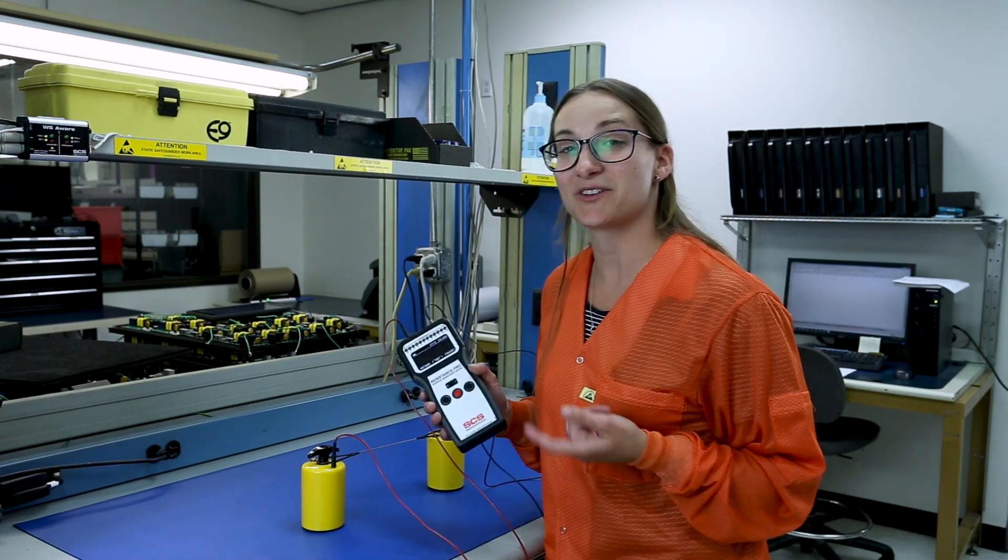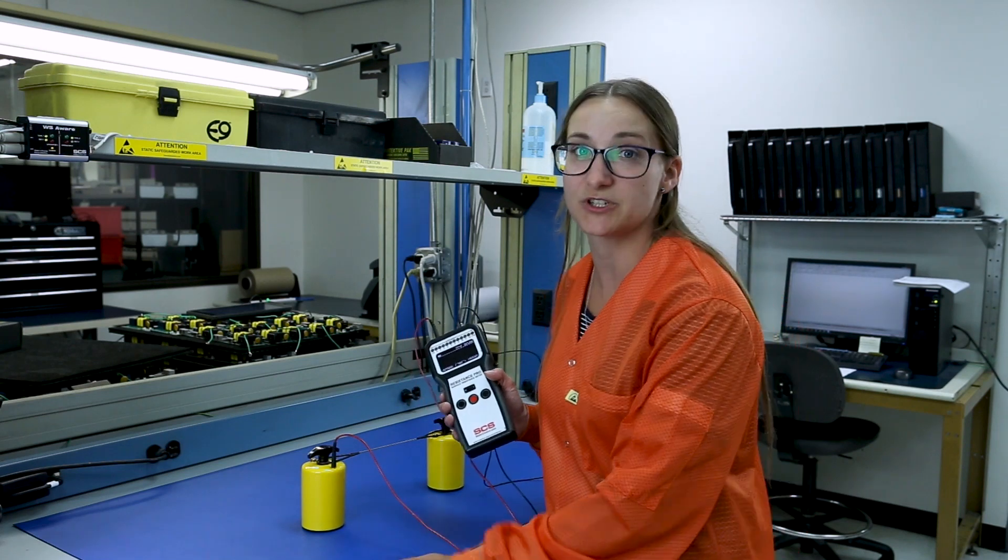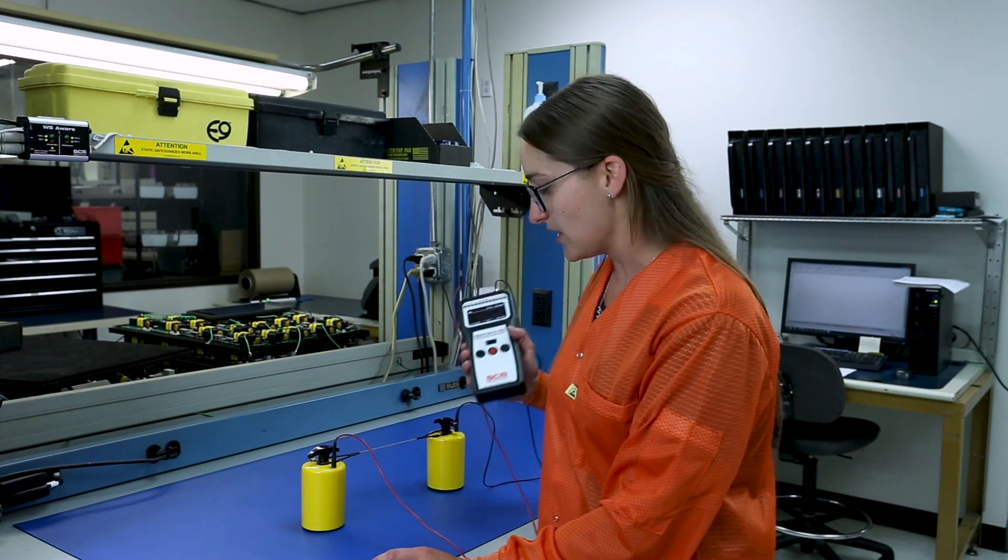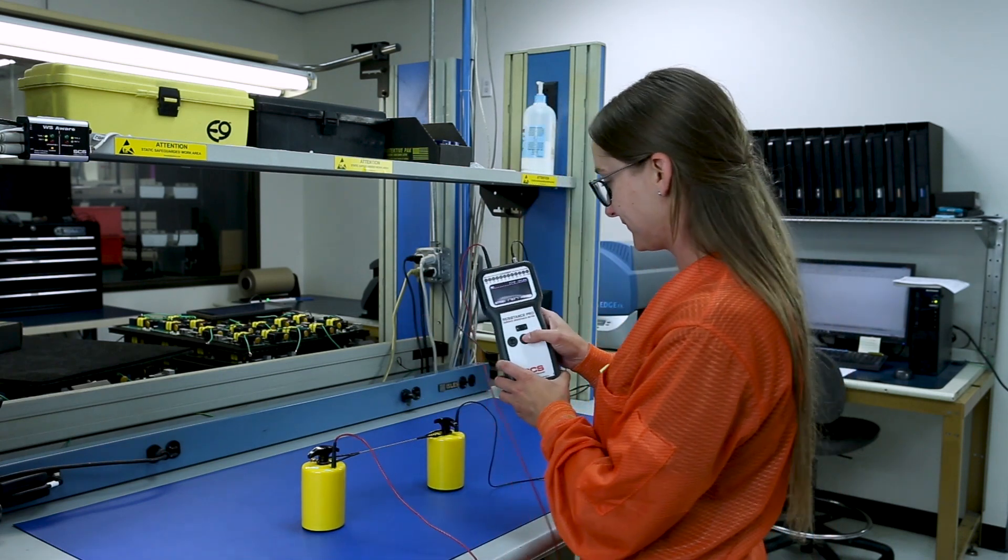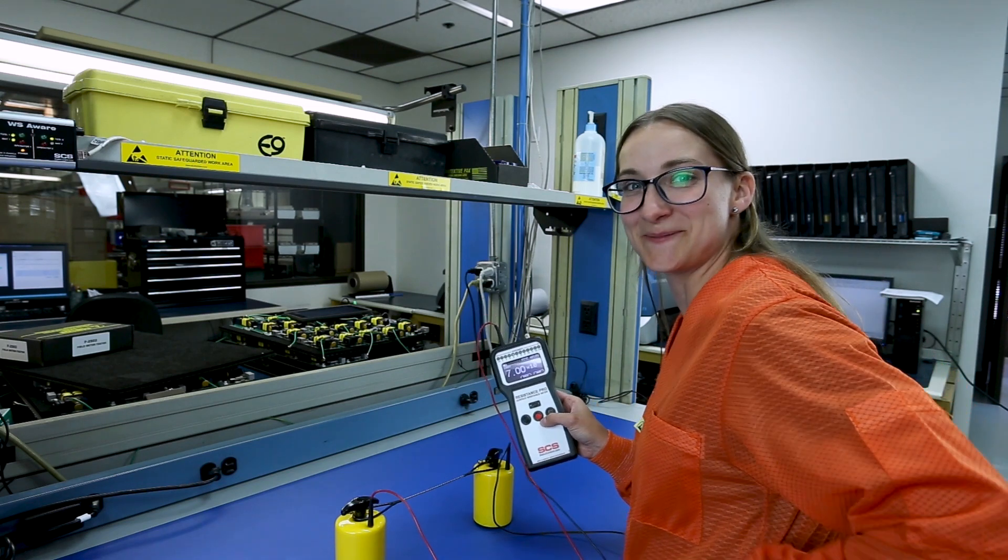We use the resistance probe to test our mats. This particular mat should test between 10 to the fifth to 10 to the ninth. So let's see what we get here. 10 to the sixth. That is definitely in spec.